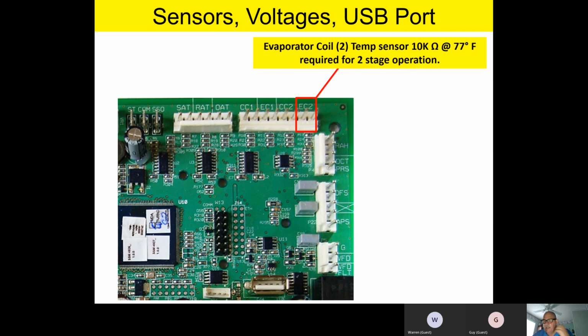If I jumpered it, it would interpret that as an extremely low ohm value. And if you take a look at our sensor chart that we just talked about, we find that you have real high ohms when it's cold, and very low ohms when it's hot. It's a negative coefficient thermistor, exactly opposite of a normal thermistor. So basically, if you jumpered it, it would think that sensor was, I don't know, pick a number, 300 degrees or something like that. And so that's a very good question.